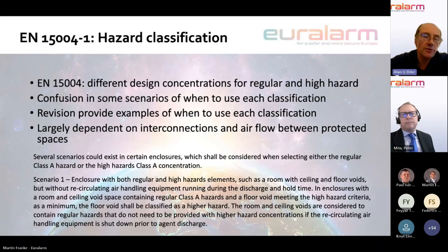And what we've found is that there has been some confusion in which circumstances to use the regular Class A or the high hazard Class A. And so the revision to the standard provides examples of when to use each classification. In bold there, I said it is largely dependent on interconnections and airflow between the protected spaces. And it's clear that in any one protected enclosure, there are different scenarios that could exist, which need to be considered when selecting either the regular hazard or the high hazard Class A concentration.